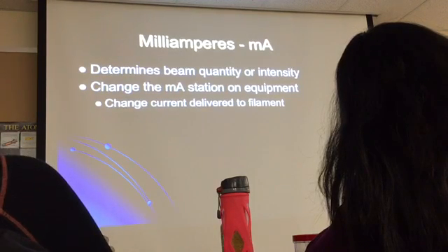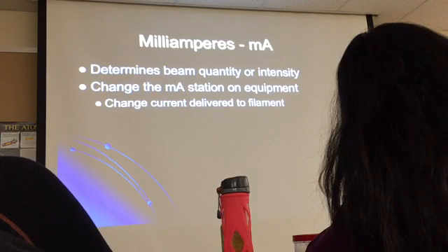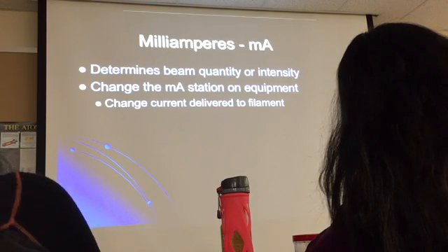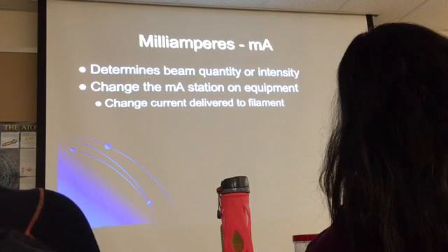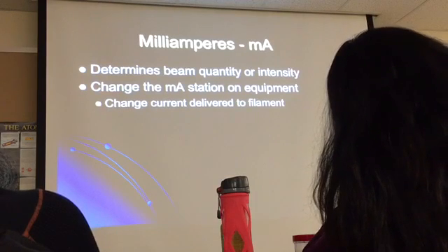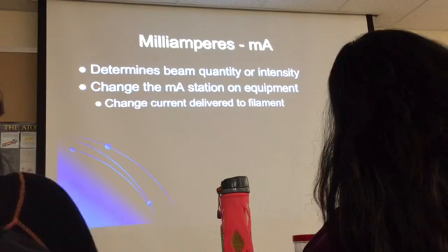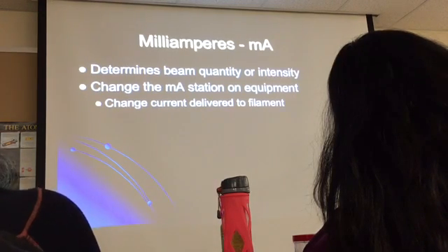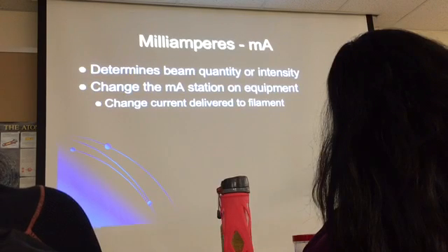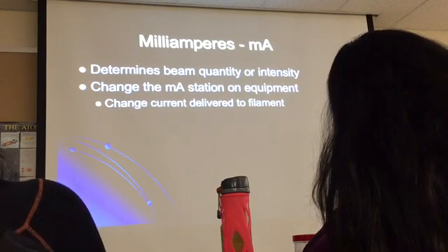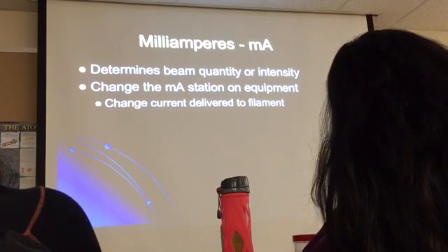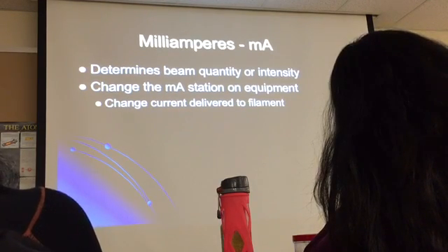What will happen if our current in the filament were measured in milliamps? Nothing. No thermionic emission. The whole reason you have amps here is so you can heat up the filament and then have thermionic emission. However, your switch in your panel, when you're changing mA, you're not really changing only that. Have you seen a switch for amps? No. It's the same switch, and depending on the milliamps you choose, it is also increasing or decreasing the amperage here.